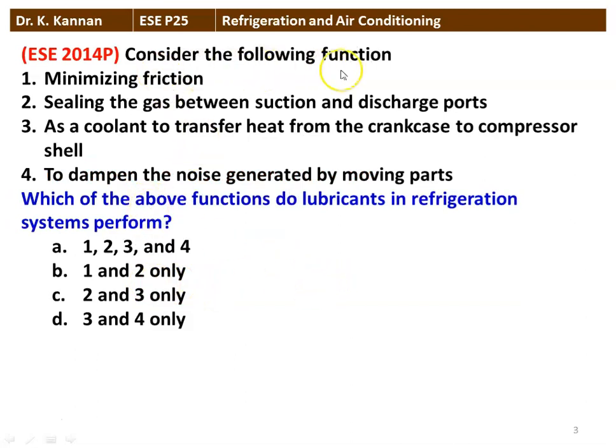Next question: consider the following functions — minimizing friction, sealing the gas between suction and discharge port, acting as a coolant to transfer heat from the crankcase to the compressor shell, and dampening noise generated by moving parts. Which of these functions do lubricants in the refrigeration system perform? All four. In a hermetically sealed compressor, such as in a household refrigerator — the black sealed body — the lubricant performs all four of these functions.